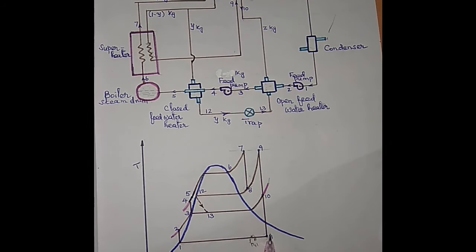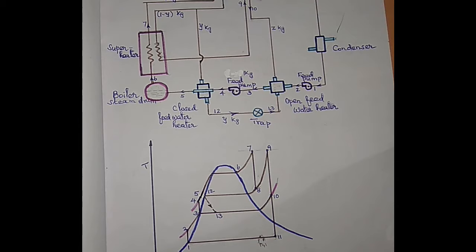So with dry steam, the internal losses will be less, the blade efficiency will improve, and specific steam consumption, as I mentioned, decreases, which decreases the amount of water required in the condenser. Okay, these are all the advantages of reheating.